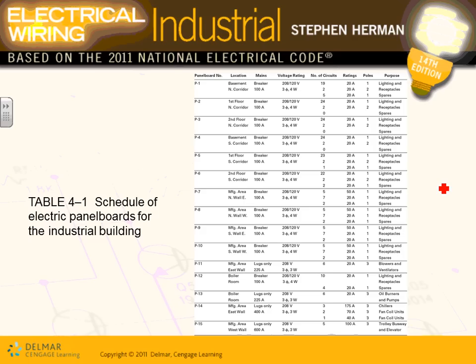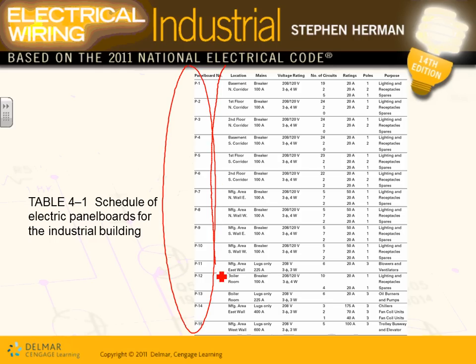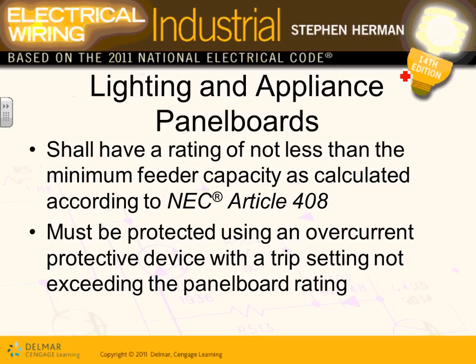The project that we have, Karen, right here, the commercial project, by the way, we have two projects, one in the book and one your Revit one. The book one has close to 15 panels. I don't know if you guys can see here, right here, 15 panels. And each one of these panels, they have a location. This is my panel schedule, the location for each one of these panels. They have the circuit breaker, the main, and the size. They have, it's hard to see, the voltage rating here. They have a number of circuits. They have the rating of each circuit, the number of poles, and what does it do for a living? Is it protecting lights or protecting receptacles? And I'll go over this one later on in a nicer format.